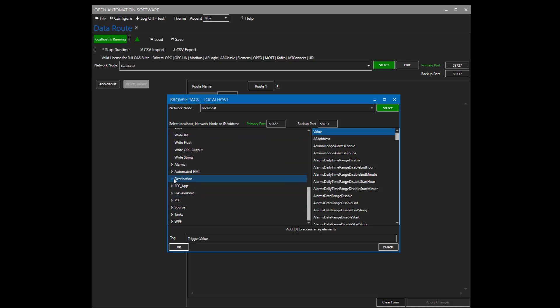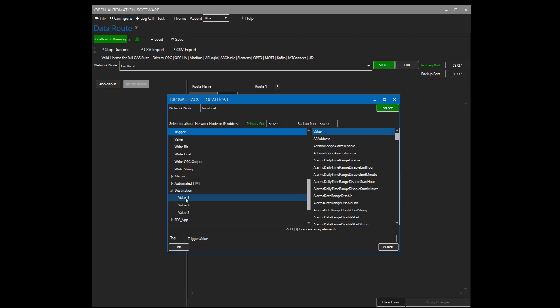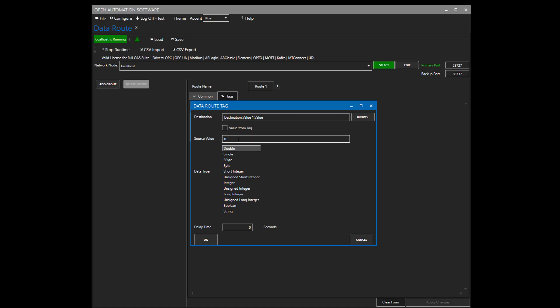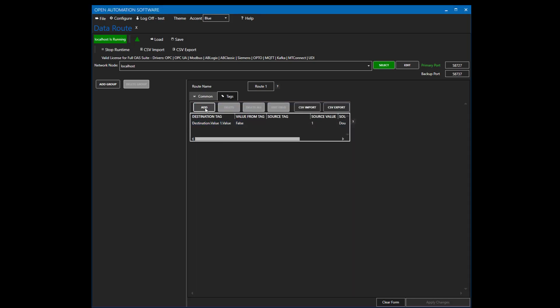I have some example tags called destination — preset double float tags: value 1, value 2, and value 3. To demonstrate writing a static value, I'll set the source value for the first tag to be 1 with no time delay. When using a static source, we need to define the data type of the value being written — we're going to typecast this string value of 1 into a double float when writing to the destination tag. Let's set up a few more tags.